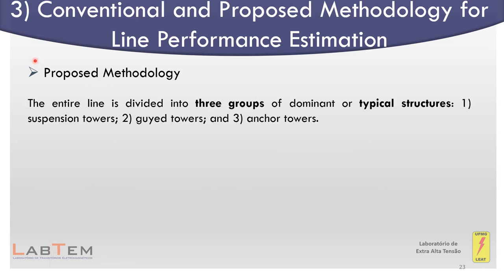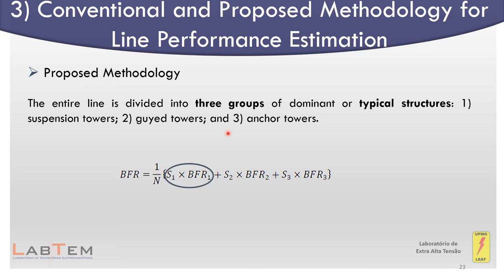In the proposed methodology, the entire line is divided into three groups of typical structures: suspension, guyed, and anchor towers. For each group, the conventional methodology is applied but considering the specific values of tower surge impedance, geometric characteristics, and specific attractive width of each group. This yields three different backflash-over rates: one associated with group one (suspension towers), one with group two (guyed towers), and one with group three (anchor towers).